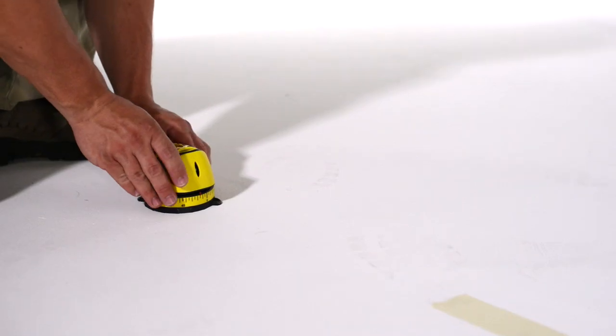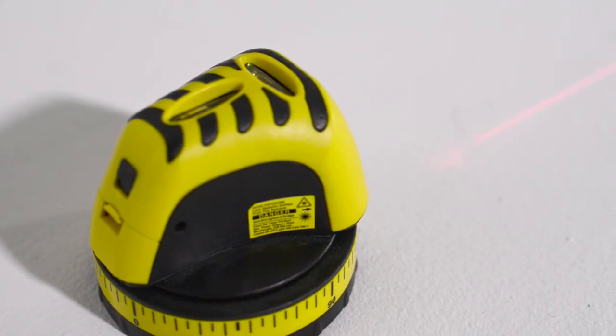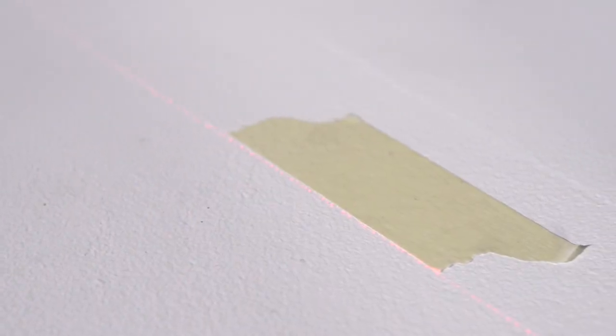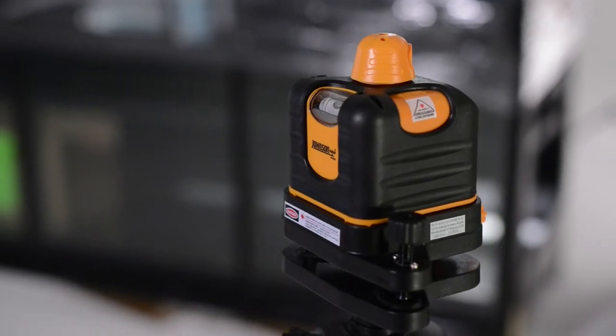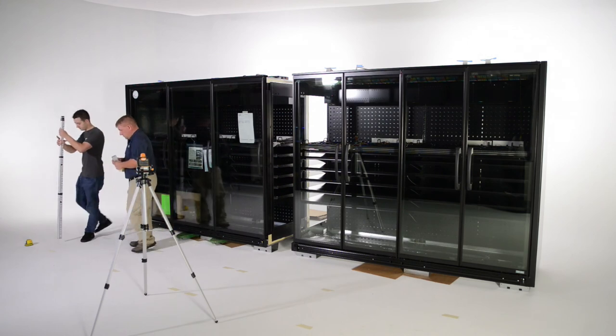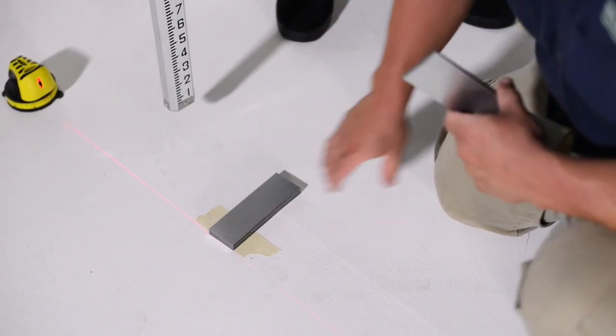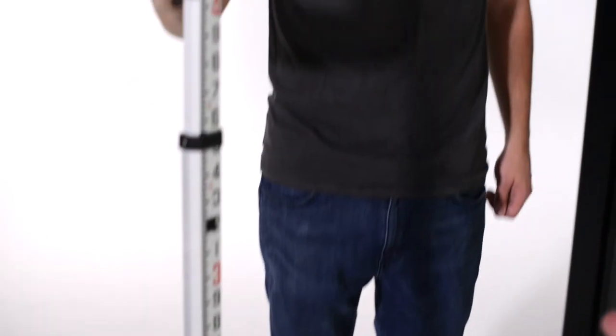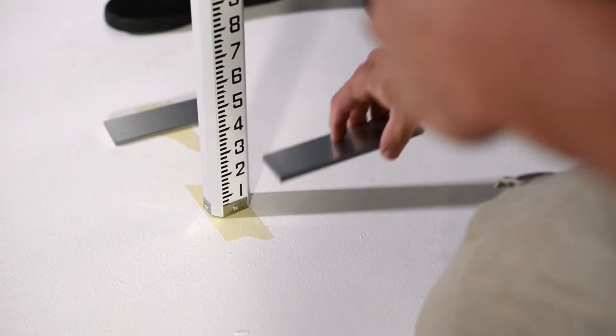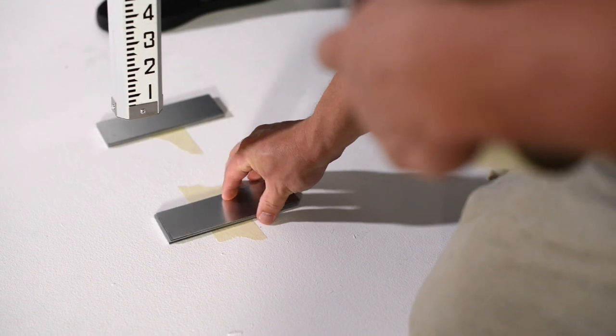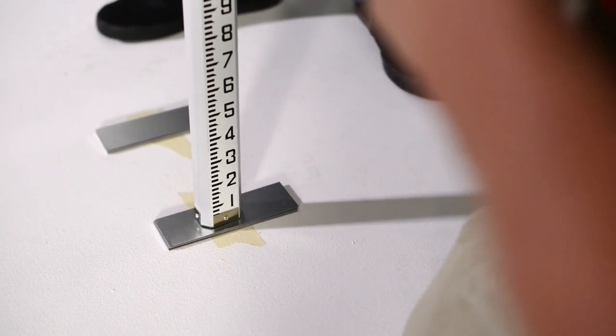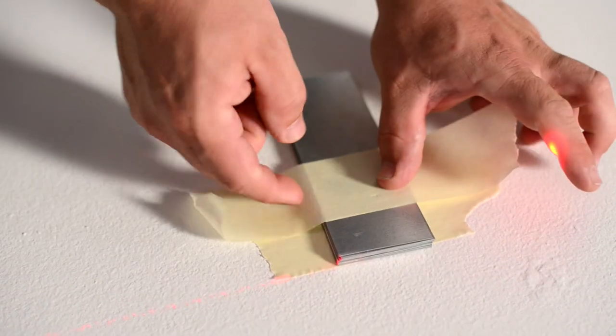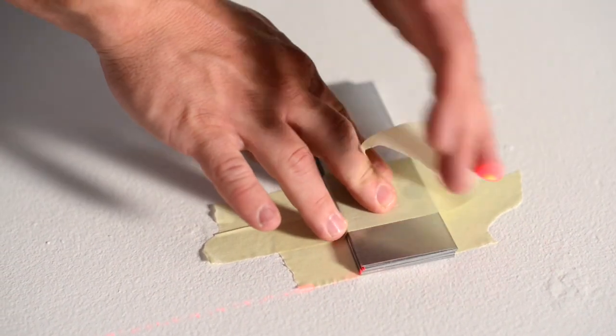Then either snap a chalk line or use a laser to mark the front edge of the lineup. Next, mark out the base plate locations on the floor with tape, then use a rotary laser level to find the high spot in the lineup and place the required amount of shims accordingly at each base plate location, both front and rear. The shims are placed perpendicular to the base plate with the front edge of shim lined up with the front edge of the base plate. This allows for proper installation of the kick plate later. Tape the shims to the floor.